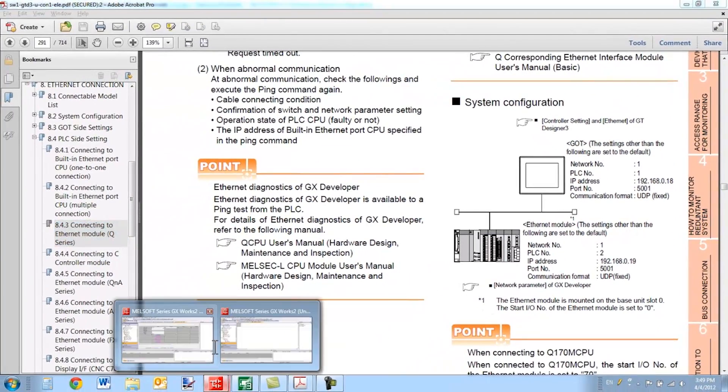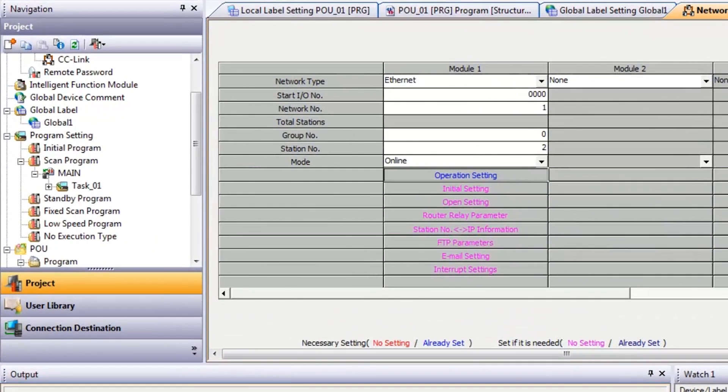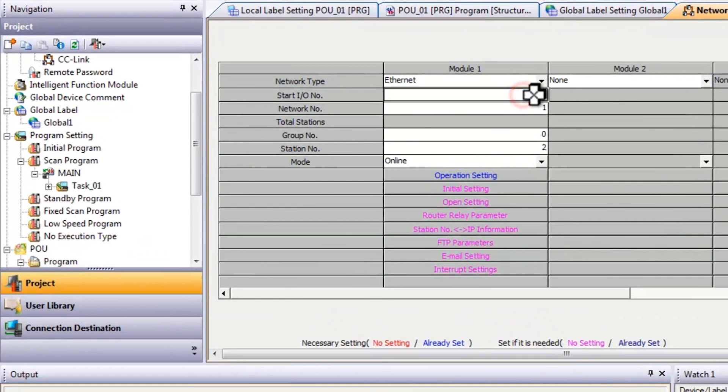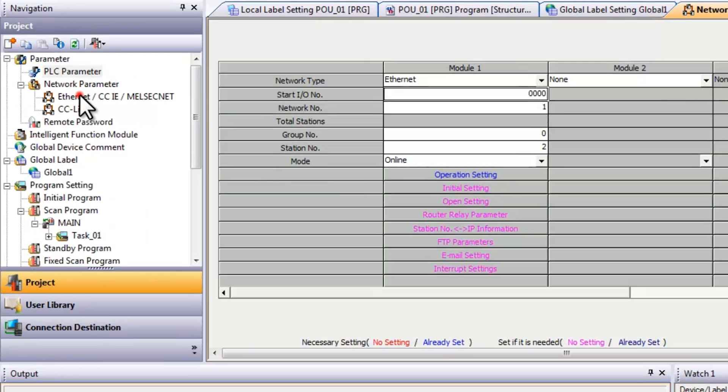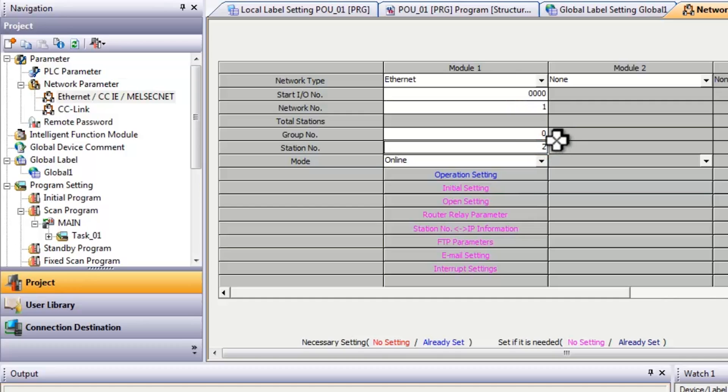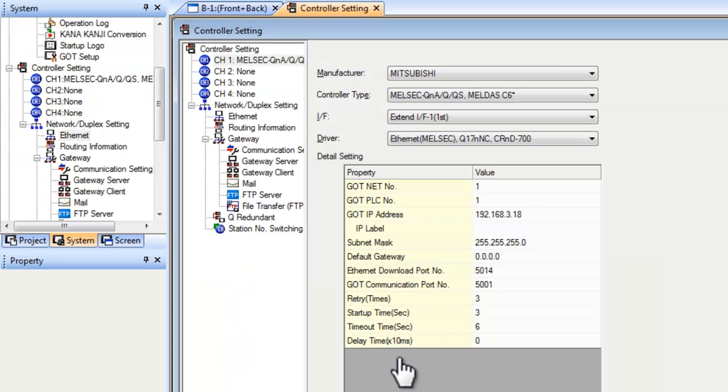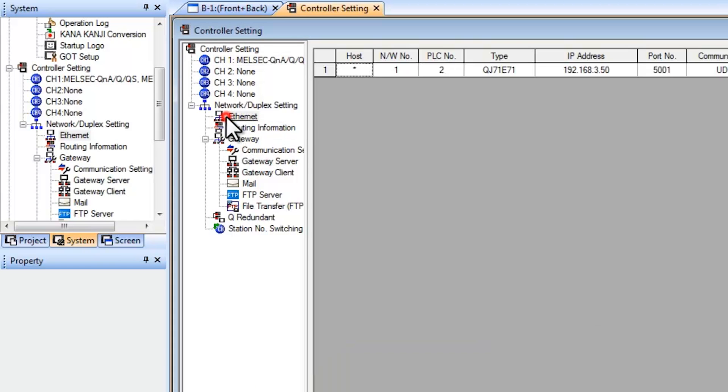And on the PLC side for the PLC program, for the Ethernet module, make sure your I.O. settings match your parameter settings. So again, in your Ethernet settings here, you would select your network number 1 and the station number. On the PLC side, it's known as the station number, it's not the PLC number, it's called station number. 2 needs to match the 2 for the PLC number on the GOT.